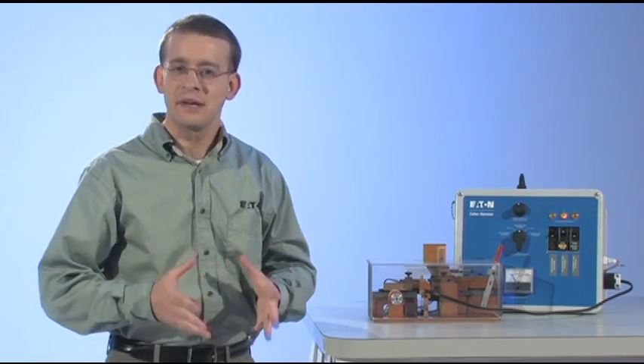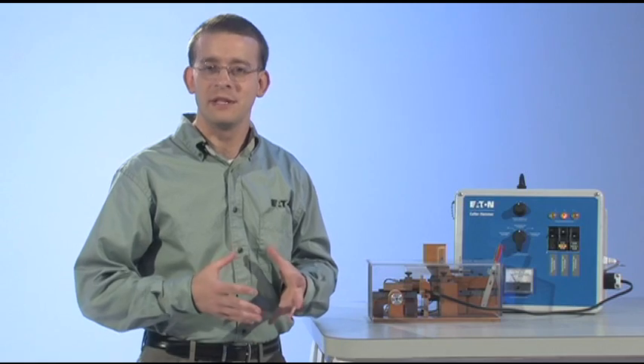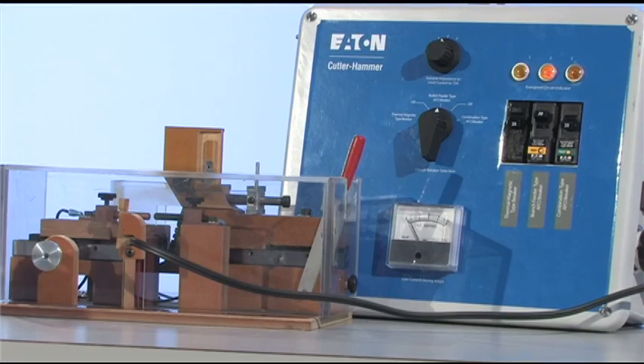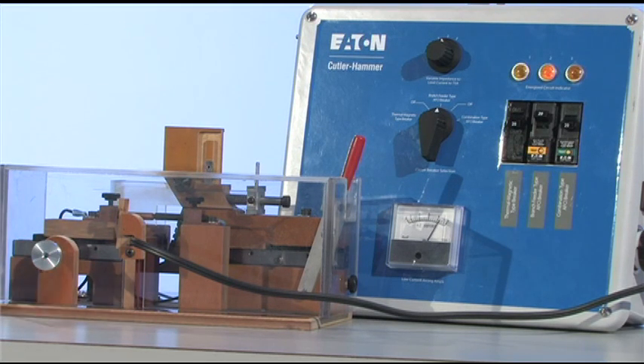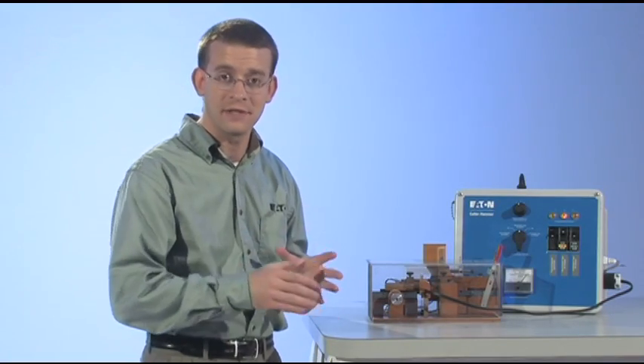Since this arc is in series with the load, the current will be limited by the loads being drawn. This low current arcing is in the 5 to 10 amp range and won't be detected by the branch feeder AFCI.